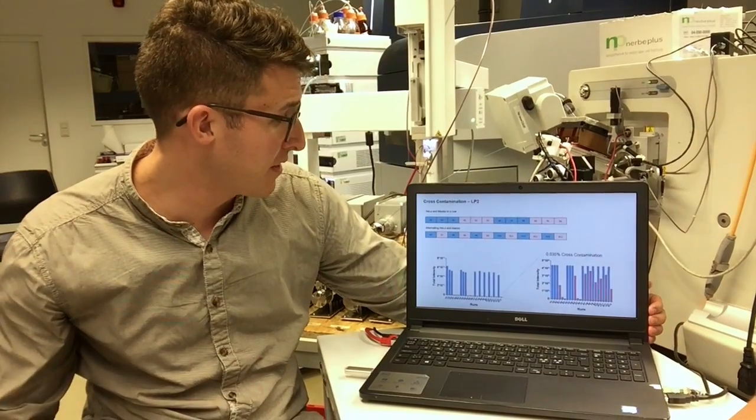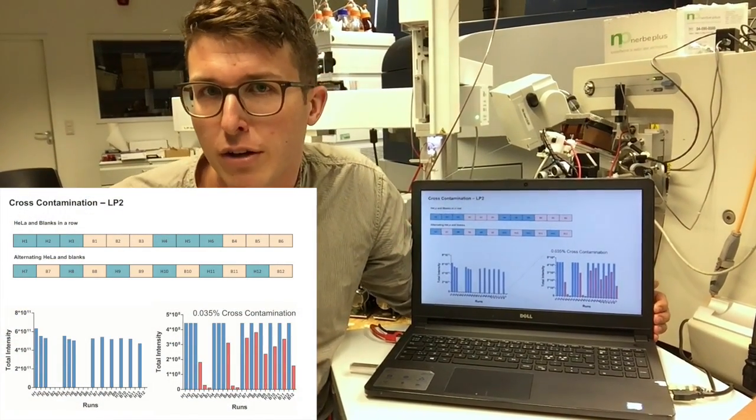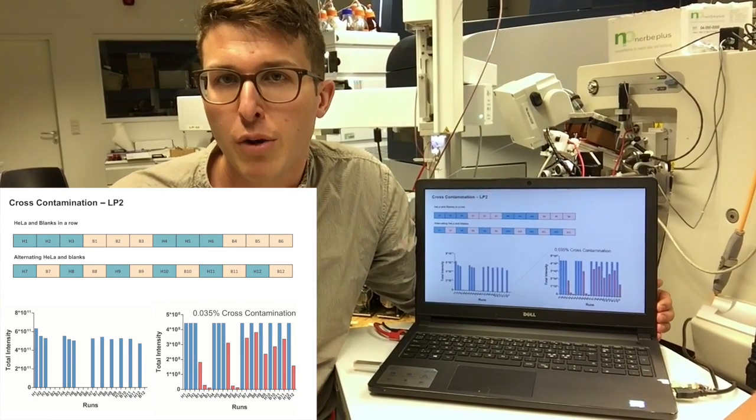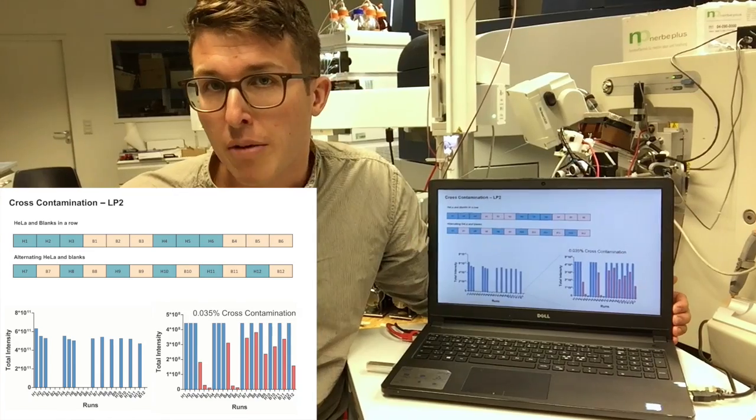And we also did some other experiments like experiments for cross-contaminations. And there we just had a cross-contamination rate of 0.03%. Which is significantly better than other nano flow HPLCs in our hand.